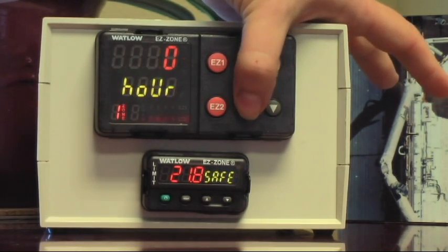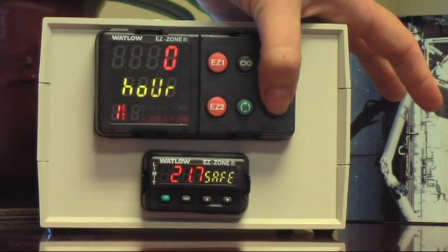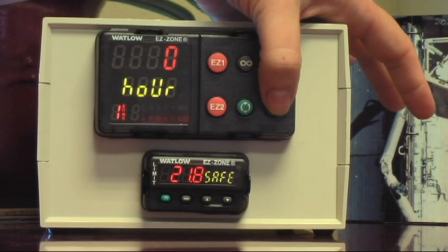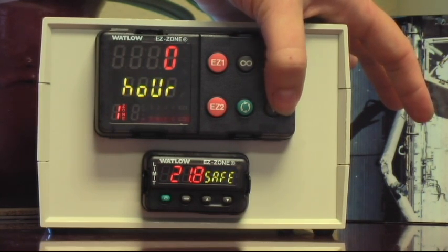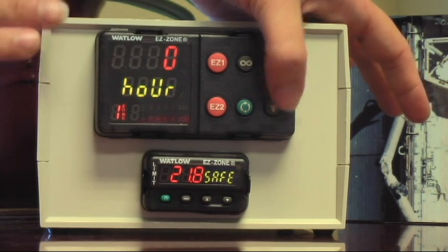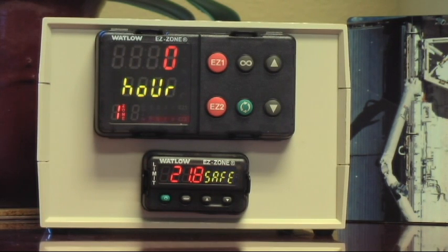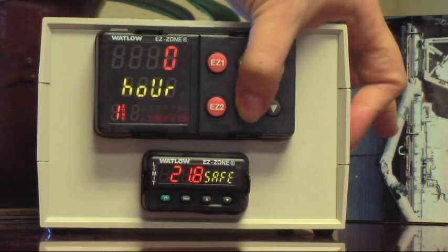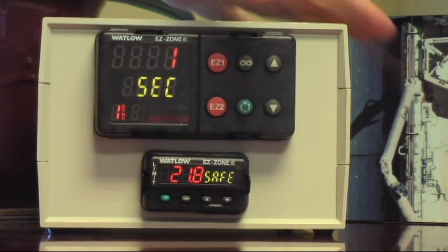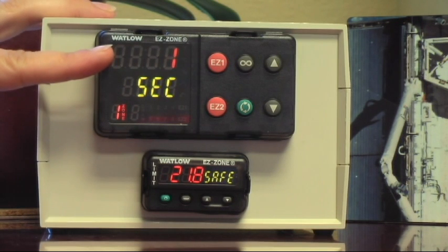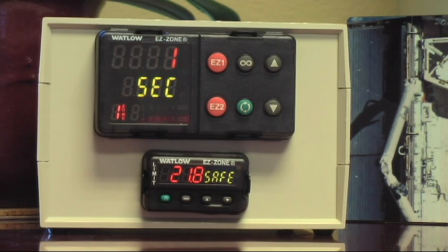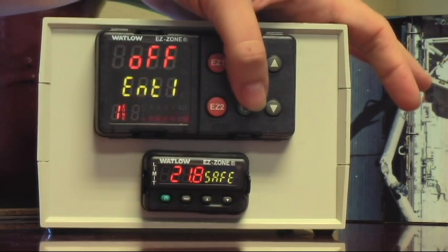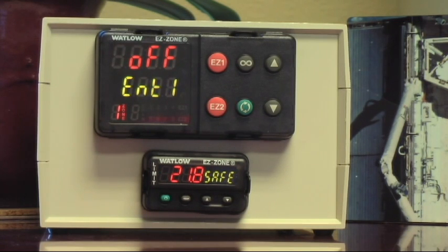Green key. Now this is not where you select eight hours. This is asking how fast do you want us to get to your set point of a hundred? As quickly as possible. Okay. But how do I know that? How do I tell it that? If you selected like four hours here, it would try to get to your set point in four hours, but we want to say go as fast as you can. So we're going to say zero hours, green button, zero minutes, green button, one second. Now a vacuum oven will take about three hours to get to a hundred and stabilize. But we're saying get there as fast as you can. Got it. So you're kind of tricking the oven and controller a little bit. We're encouraging it to go as quickly as possible. We don't trick. We encourage.